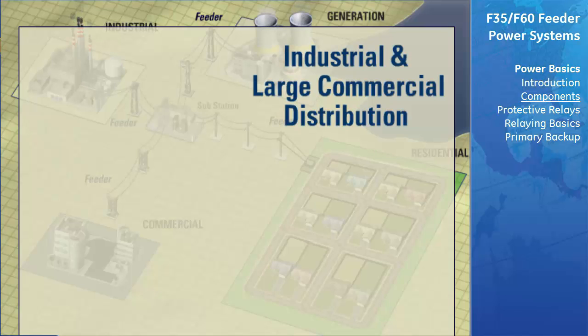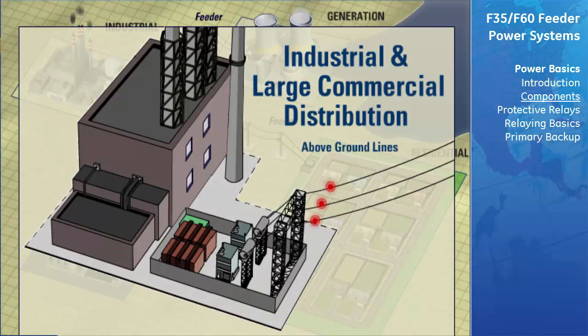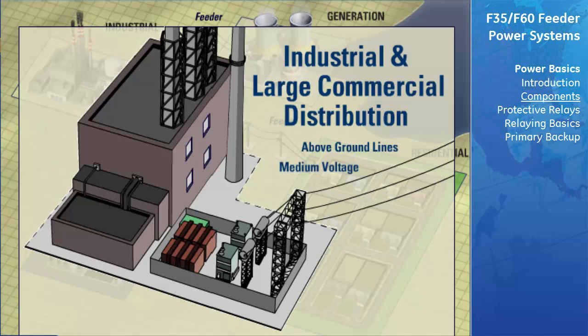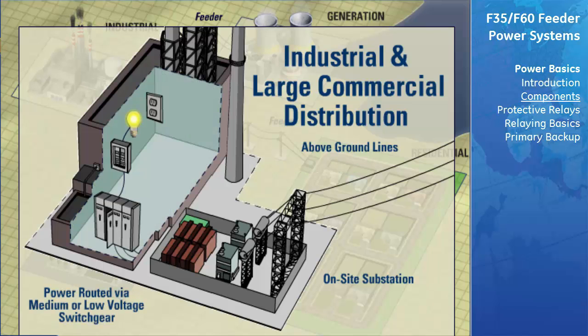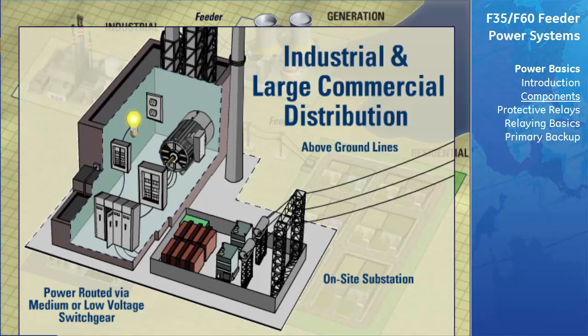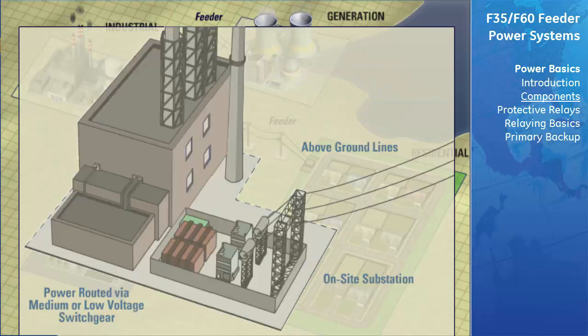From the substation, industrial or commercial power lines take the power above or below ground to a large transformer, which steps the three-phase voltage down to a suitable level for the plant or building. For larger commercial or industrial users, this voltage may be in the medium voltage range, and in that case there will be an additional substation on site. The power is then routed from the transformer via medium or low-voltage switchgear to different areas of the plant or building for further distribution via switchboards and panel boards.